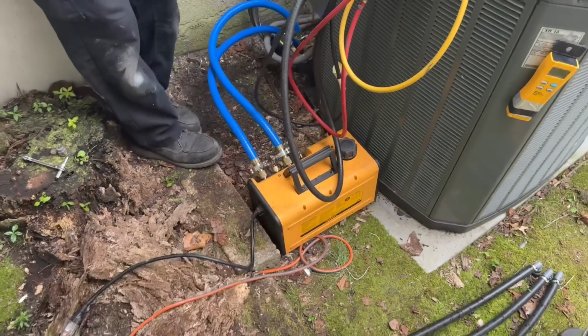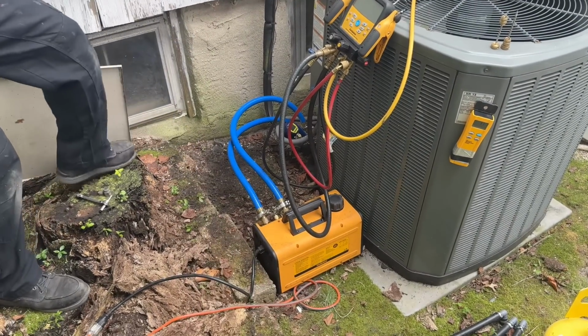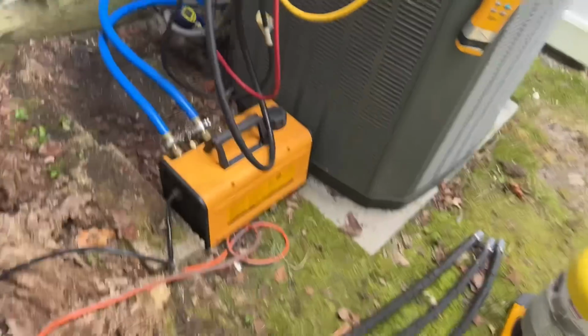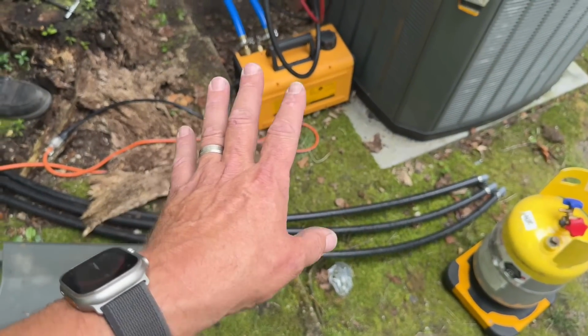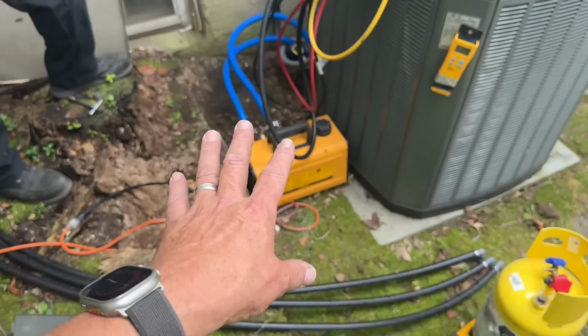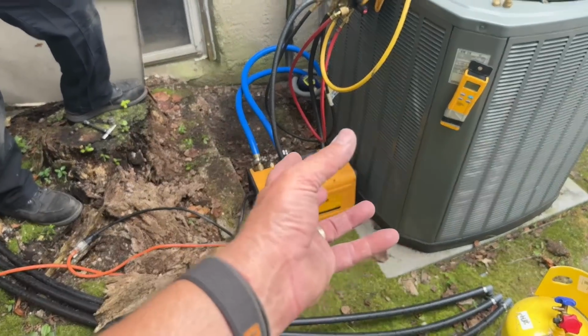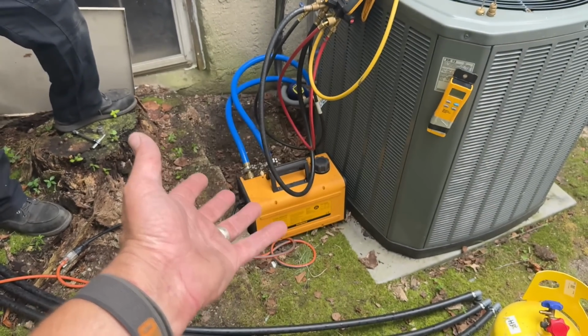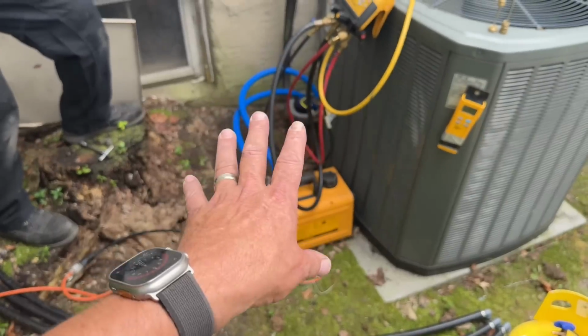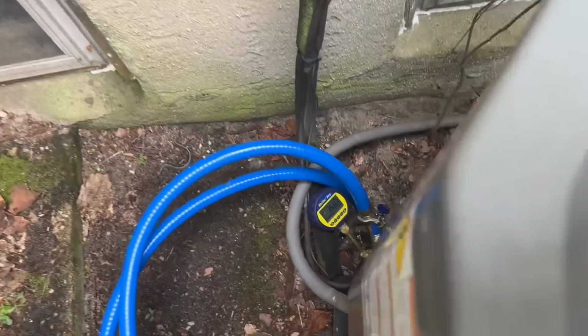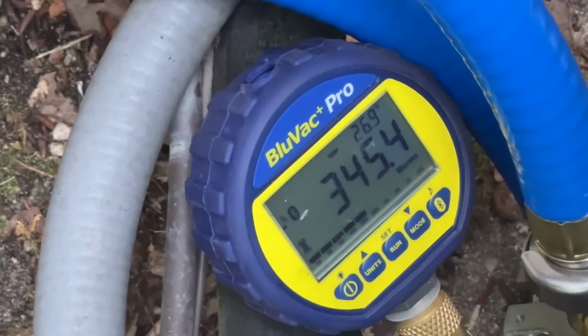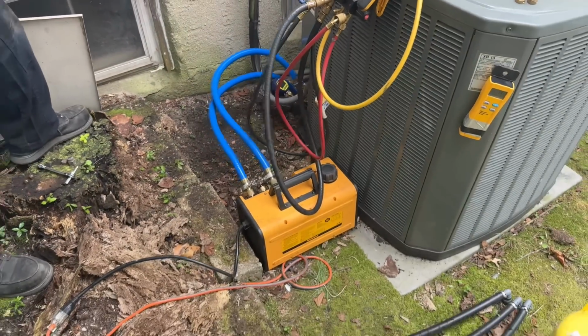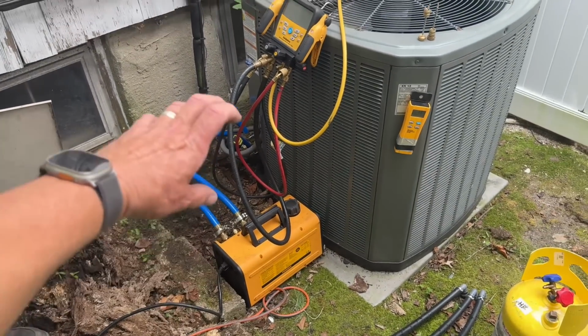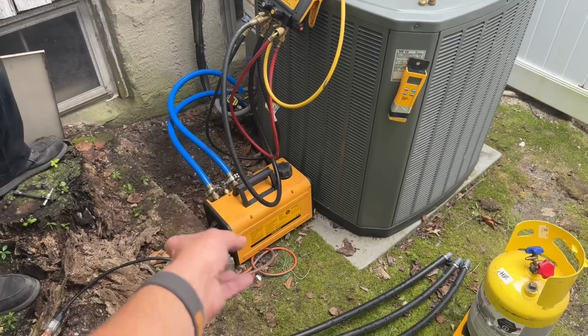Okay, if you notice what Daniel just did, which decreased the noise on our vacuum pump, when we initially turned on the vacuum pump, we had this little lever there. That's for the gas ballast. So the gas ballast was open, right? And that's allowing us to vacuum without having to pull through the vacuum pump oil, and it increases the life expectancy of that, right? So once we get to around 1,000 or 1,500 microns, right now you're gonna see we're 350. See? 344, 342, 330-ish. So once we get to around 1,000 or 1,500, you're gonna close that ballast, and now you're gonna pull the vacuum through the oil and then out of the machine.